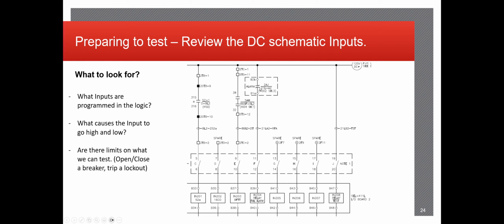You also look at alarms from other relays that may be coming in. Again, these relays might be in service, so the only way to test them would be to isolate them completely and cause an actual relay fail to occur. This is all stuff that you always want to look over and understand what the risks may be, and then try to mitigate them as best as possible.